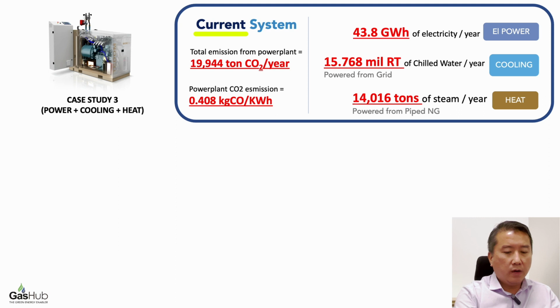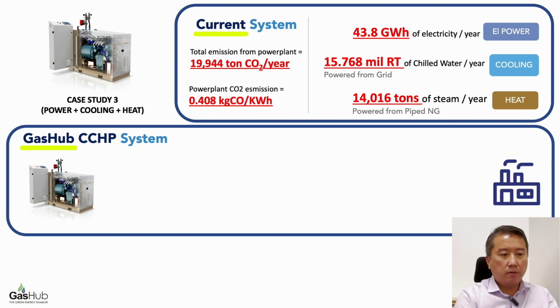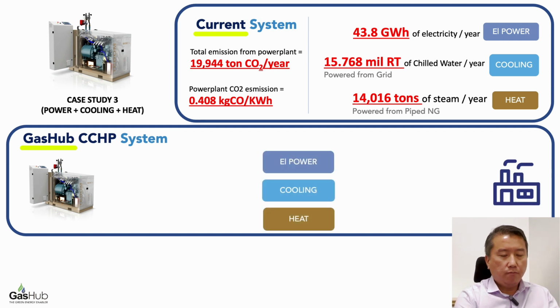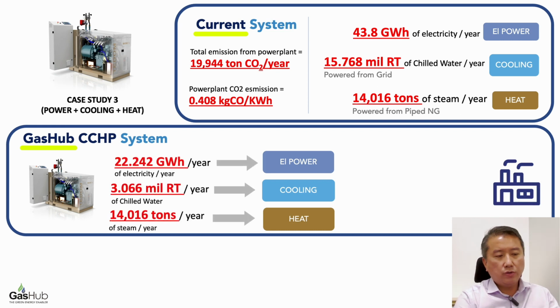So after analyzing their requirements, we put in place a combined cooling, heat and power system, and this system produces electricity, cooling as well as heat on site. We produced about 22 gigawatt hour of electricity per year supplying to their use, and at the same time we recovered the heat coming from the system to produce around 3.066 million refrigeration ton of chilled water per year. And we are also able to recover all the exhaust heat coming out from the system to produce about 14,000 tons of steam per year.